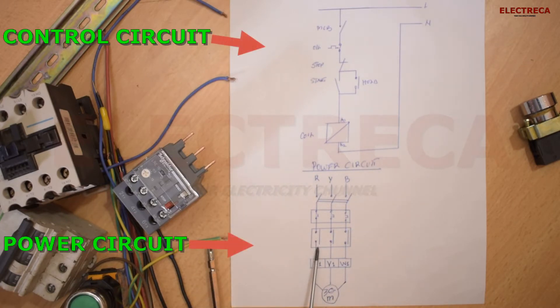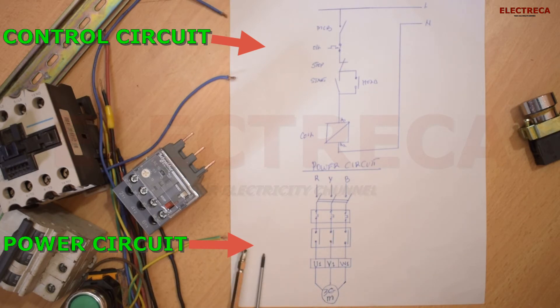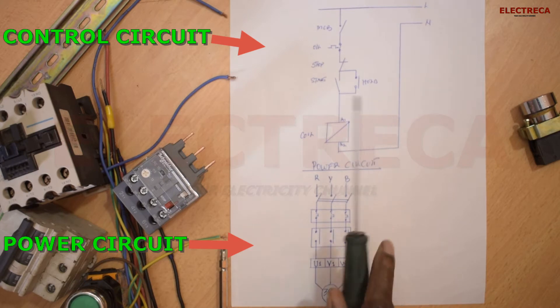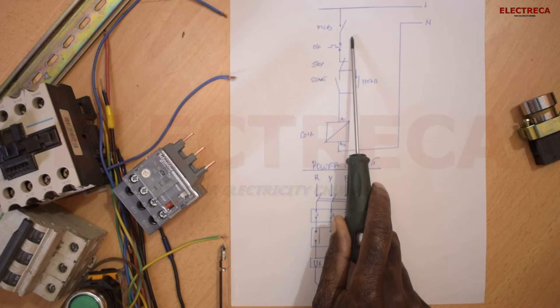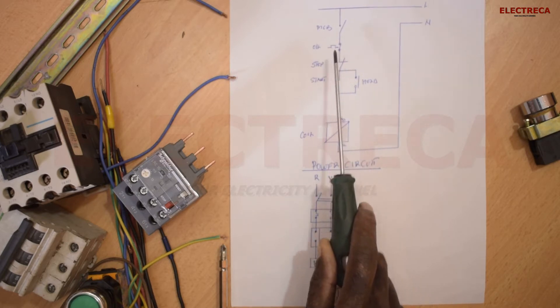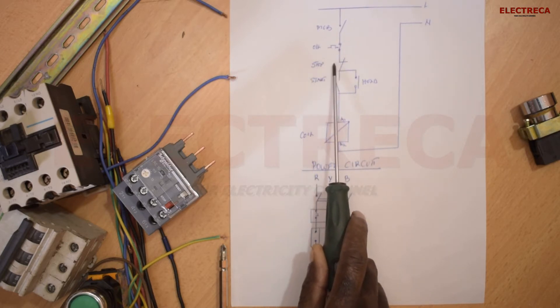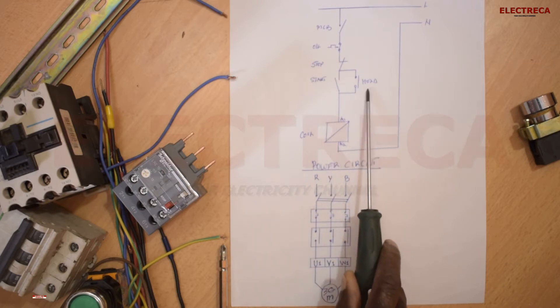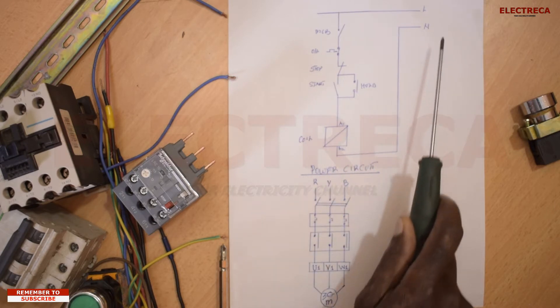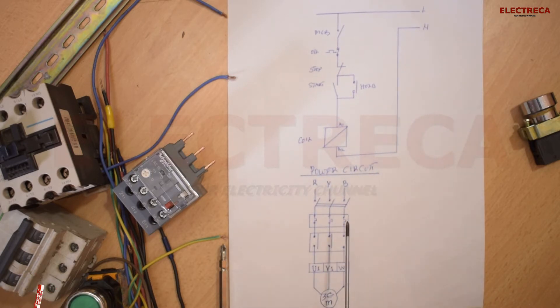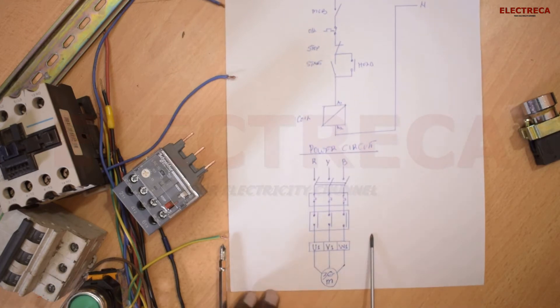Now I have two circuits here - we have got the control circuit and we have got the power circuit. Now our control circuit, if you see, comprises of this MCB, then you have your overload, then you have your stop, you have your start, you have your hold, then you have your coil. And then your control circuit takes a live and a neutral.